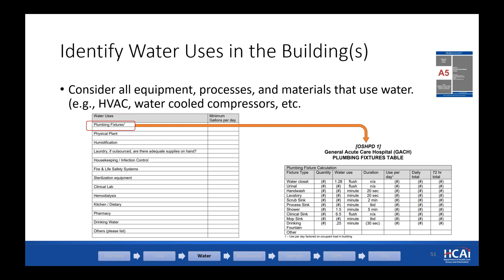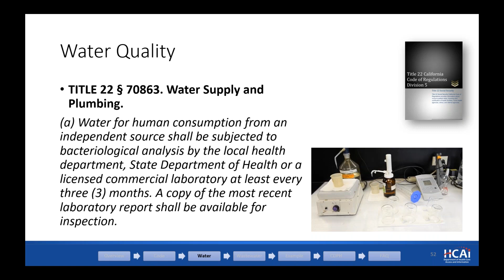Water quality. This is a Title 22 requirement, not HCAI, but a CDPH requirement. What it states here is that water for human consumption from an independent source shall be subjected to bacteriological analysis by a local health department. It says something like at least every 3 months, and a copy of the most recent lab report should be available for inspection.